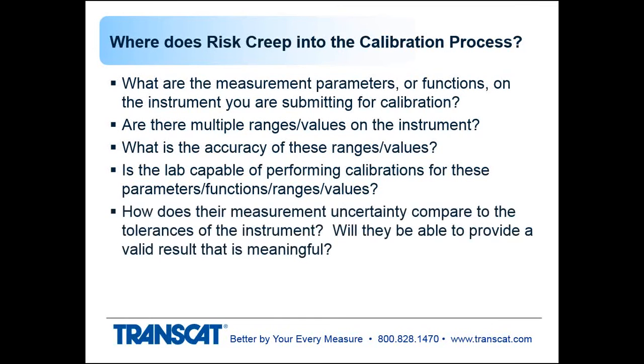How does their measurement uncertainty compare to the tolerances of the instrument? This is where we get into ratios, whether it's an accuracy ratio or an uncertainty ratio. Here we're talking about uncertainty of the lab, so it would be an uncertainty ratio where you're comparing the tolerance of the instrument at each of its different readings to the uncertainty of the laboratory at each of those different readings. And is the lab providing an uncertainty that results in a meaningful or valid ratio? Now, the acceptable ratio is going to be based on what your standard operating procedures are for your company. Most of the time, that's 4 to 1 or better. Sometimes it's different levels.